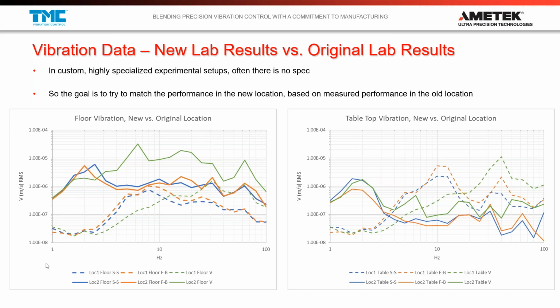What we also saw, taking measurements of the tabletops, was something that really echoes what you would expect to see on the floor. The tabletop is pretty quiet. It's behaving relatively like a rigid body in the original location, and then you start to see the resonances of the supports.